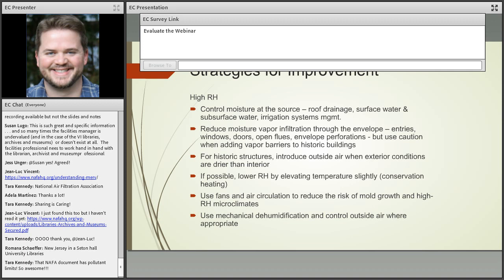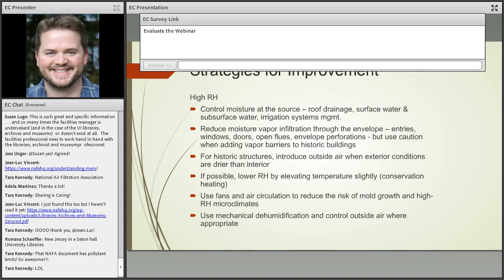We had another question here from Tara. She said that she encountered a desiccant wheel setup where they were using the heating coil to dry out the moisture on the wheel. She's been arguing that it needs to be superheated and the heating coil that exists in the AHU isn't sufficient. She's just wondering if she's right about that. Right and wrong are very loaded terms.